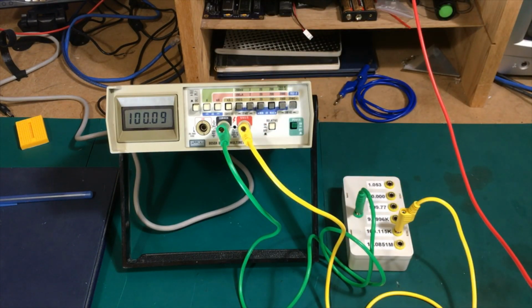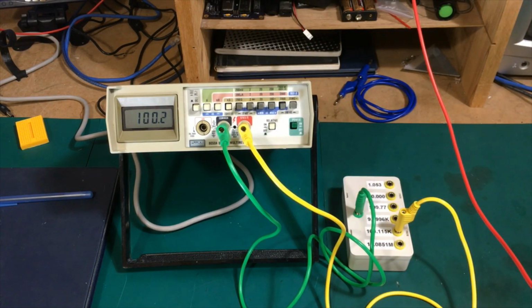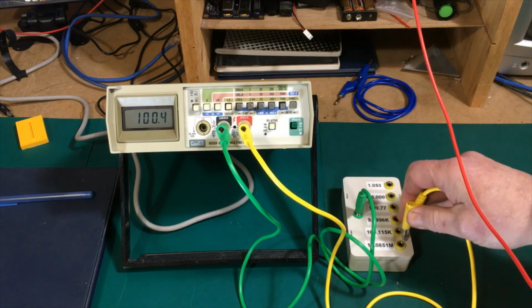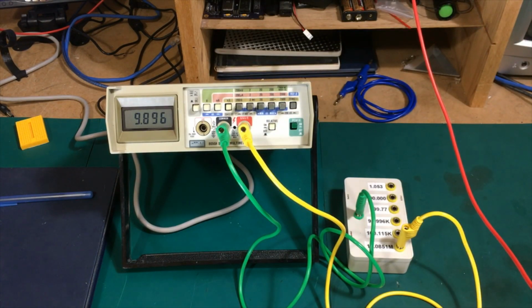Now this next range here, we'll check two ranges with this resistor value. So this one here should be between 100.05K and 100.19K, and yeah, we're doing good there. We're in the middle of that range too. Now if we go up to the next highest range, this same resistor should read 99.6 to 100.7, and yeah, we're in the middle of that range too. Now the final one, check the highest ohms range here. This should read between 9.805 and 10.365, and there we are, right in the middle of that range as well.